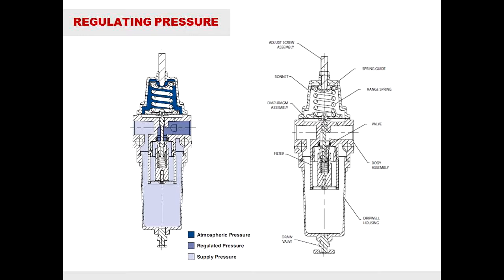The range and set point of the regulator is determined by the range spring. The spring coefficient of the spring determines the range and how far the spring is compressed determines the set point. This set point can be field adjustable via the adjustment screw located at the top of the housing.